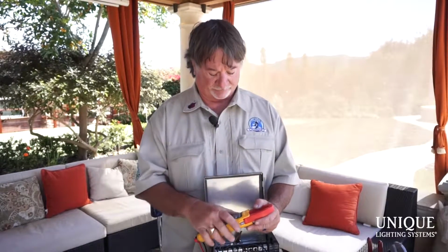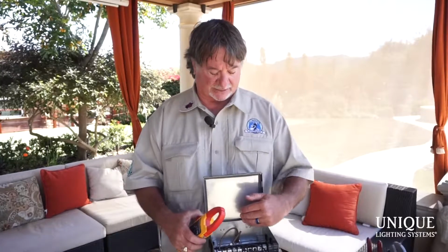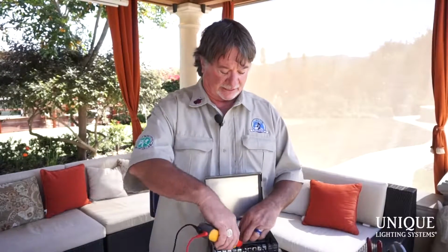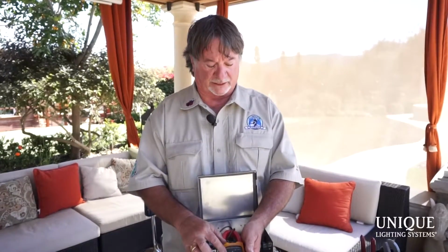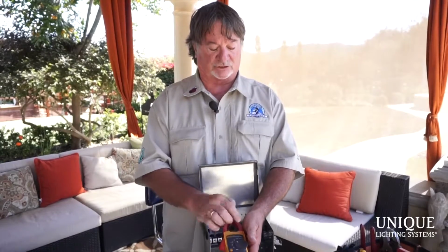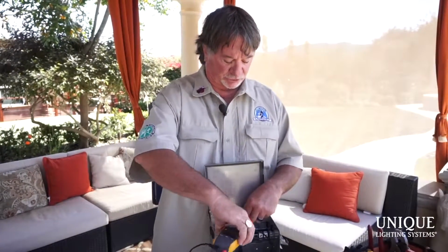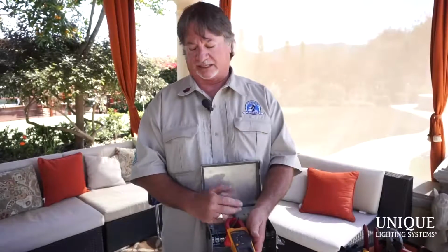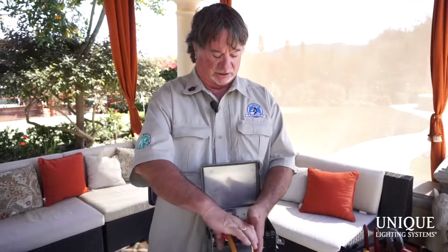What did they add? At this point, I come back, because I might have multiple wires here. Run number 9 used to have 1.6, still has 1.6. I go to run number 2, it used to have 1.4, now it has 15. That's my problem run. I look at the description, hub number 2, go and identify the problem, and start my process of elimination. This is key for troubleshooting.